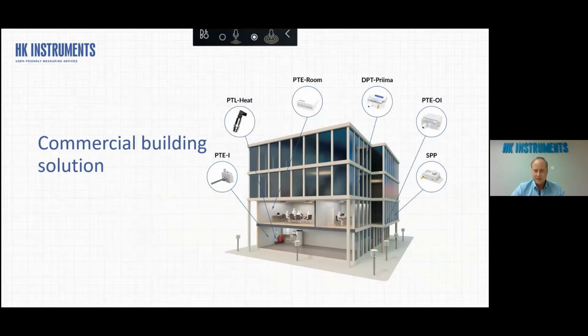And then in Finland we have this new way to monitor how well the building is sealed, because we want to make sure that the building pressure, inside pressure compared to outside pressure, is almost zero. We typically want to set the differential pressure over the building envelope slightly under pressure, but we never want to go over pressure, because otherwise, here in Finland, for example, we have very moist air, and if we push the moisture and the bacteria to the walls, it can cause mold over time.